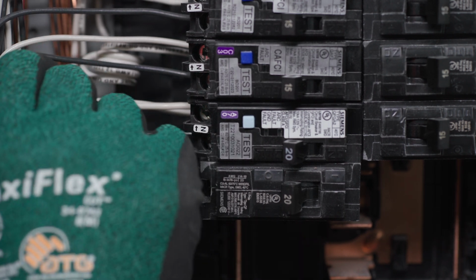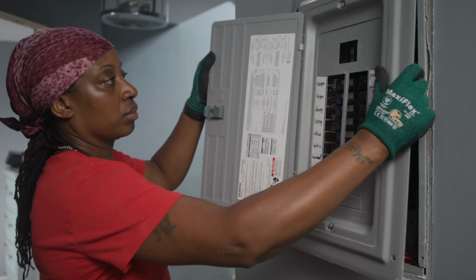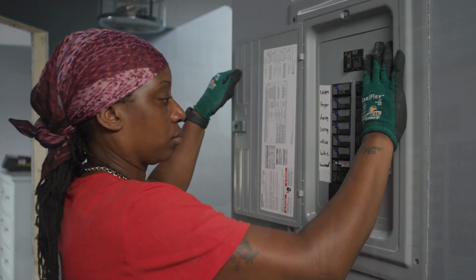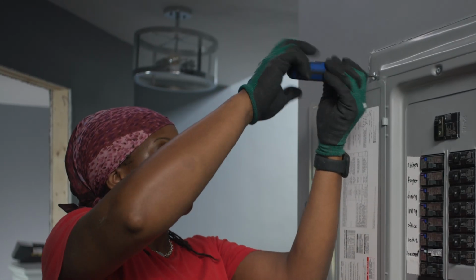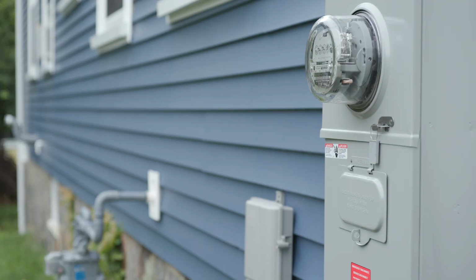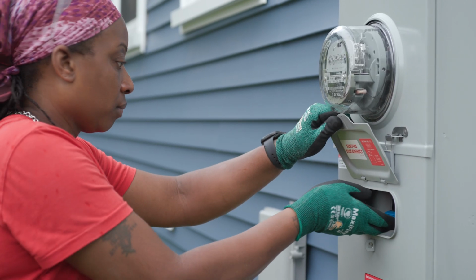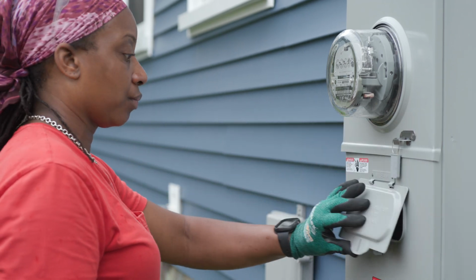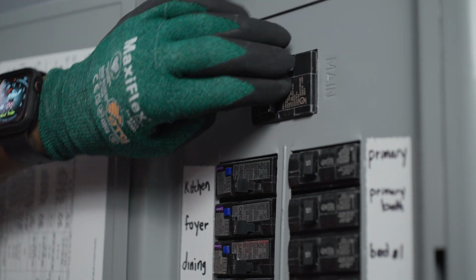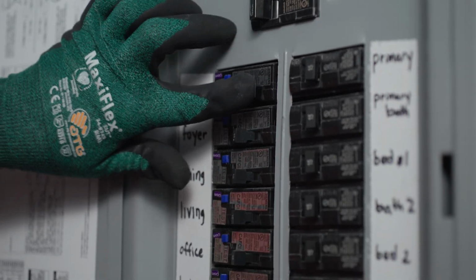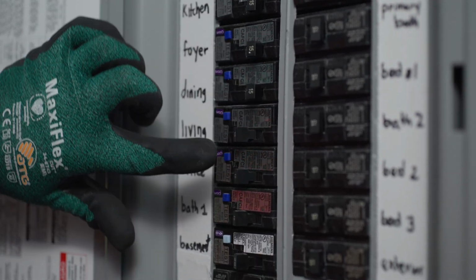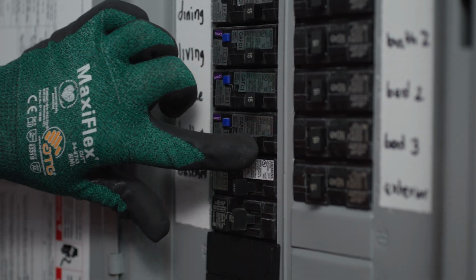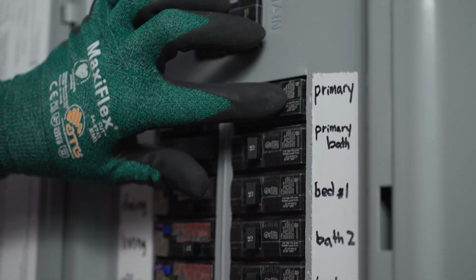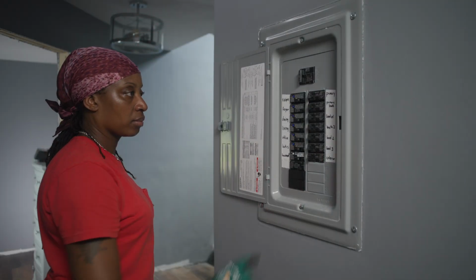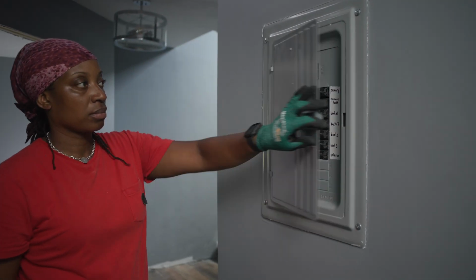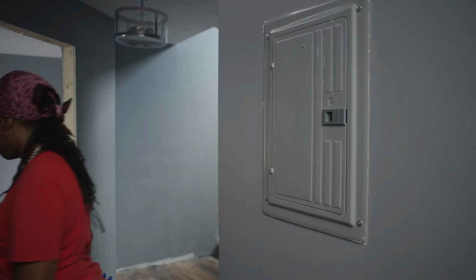Check that all connections are tight and then screw the breaker panel cover back in place. Now, turn the main power back on, then turn on the main breaker at the panel, followed by each of the individual breakers, one at a time, so that a lot of equipment won't be starting up at the same time. Finally, test the AFCI breaker by pressing the test button on the front. The breaker is working properly if it trips open.